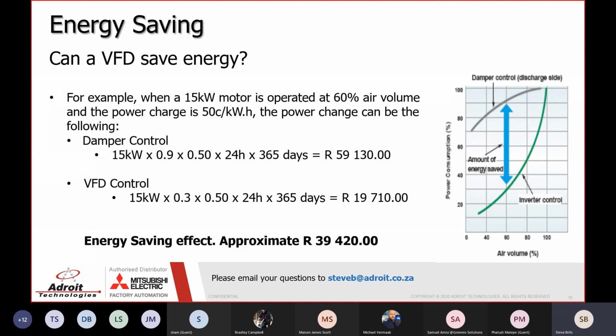Using a damper controller, for instance, a valve or a damper for damping airflow, I've done the following calculation: if you run that motor with your damper controller for a full year, the electrical bill will be 59,130 Rand. Using a VFD for the same amount of hours and same amount of airflow, where you control the speed instead of using a damper, your electricity bill will come down to 19,710, which gives you approximately a saving over a year of 39,420 Rand.